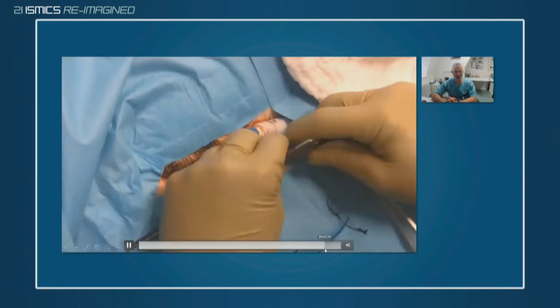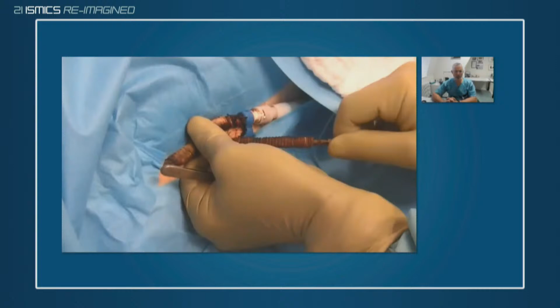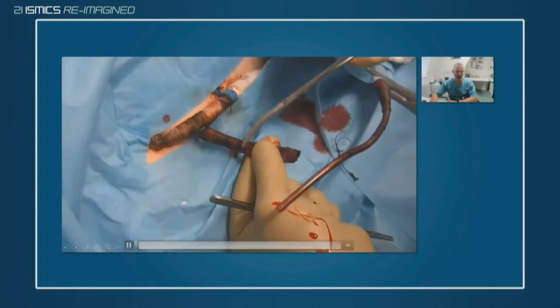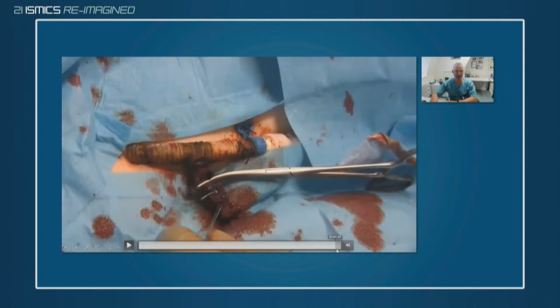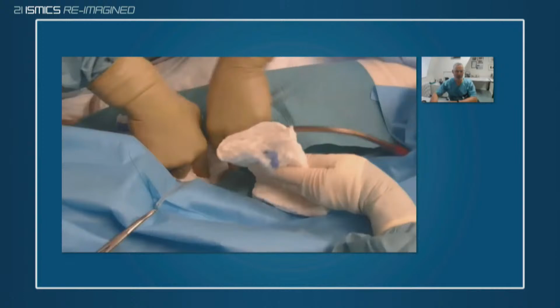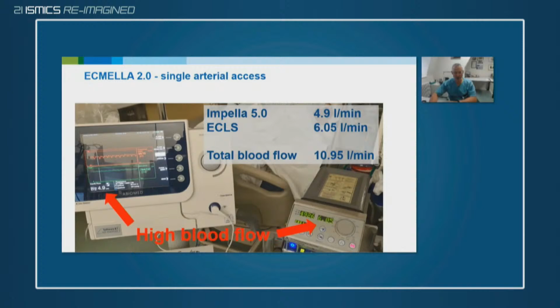So, de-escalation is also very easy. Bedside in the ICU, just clamp and remove the arterial cannula from the branch, clamp the branch, ligate it, and the same is for the venous cannula. The venous cannula will be removed from the groin and secured as usual. So this combination may provide up to 11 liters flow, as you can see here, 6 liters on the ECLS and 5 liters of Impella, which is very important. In a patient in SIRS situation, high perfusion leads to reduction of vasopressors.